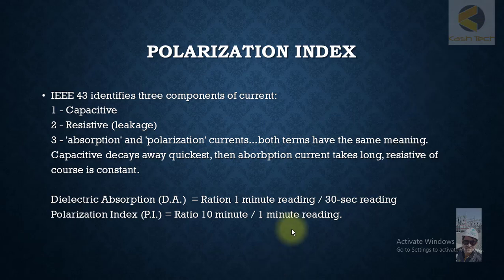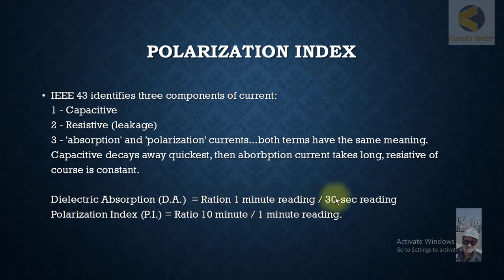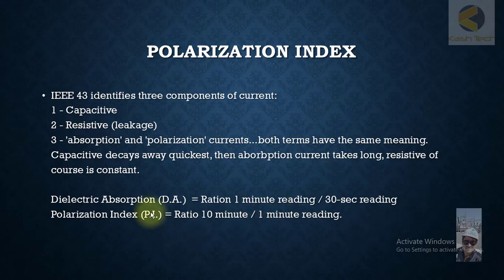Hey guys, now we will discuss the topic in which we will compare dielectric absorption versus polarization index. The formula for dielectric absorption is basically the ratio of 1 minute to 30 seconds, where the polarization index is the ratio between 10 minutes to 1 minute. This is just a difference of formula between these two.